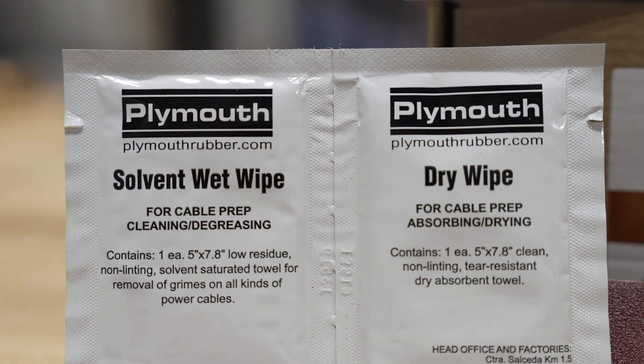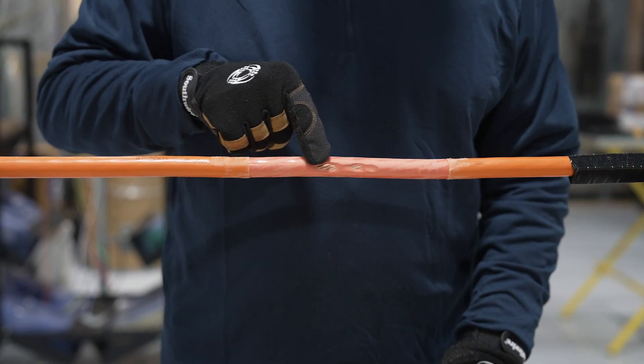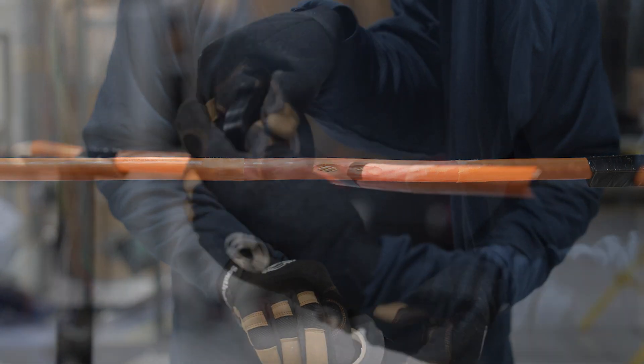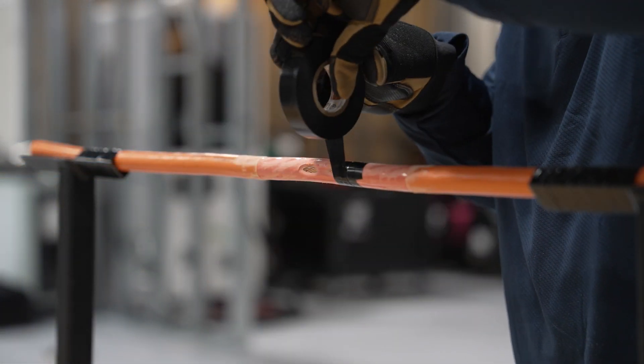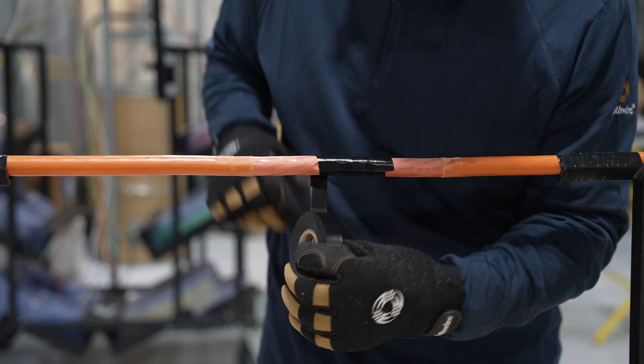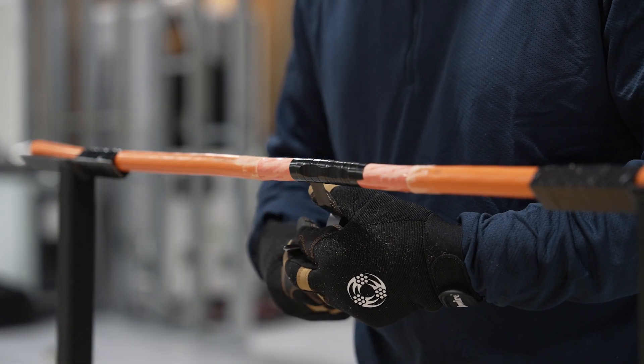Step 4: Clean the abraded area using a solvent wet wipe and dry with a lint-free wipe. Both wipes are included in the kit. If the aluminum or copper conductor in a single conductor cable, or the metallic shield in a shielded cable is exposed, apply one half-lapped layer of RE3-2 protective vinyl finishing tape to cover the exposed metal. Skip Step 5 if there is no exposed metal.